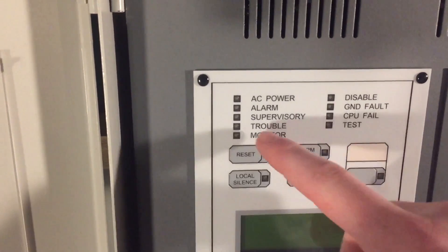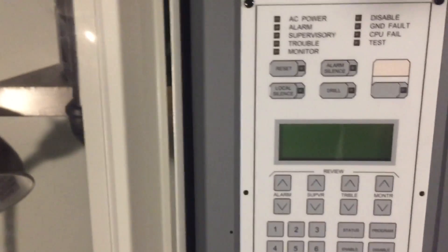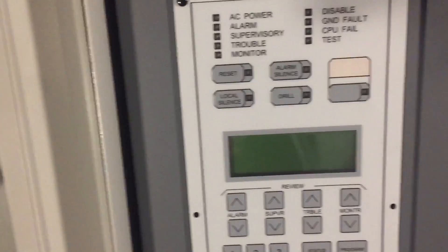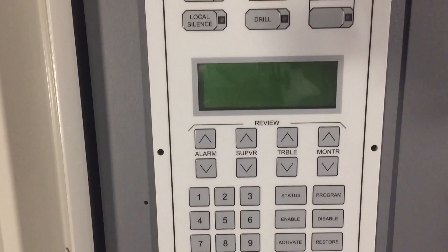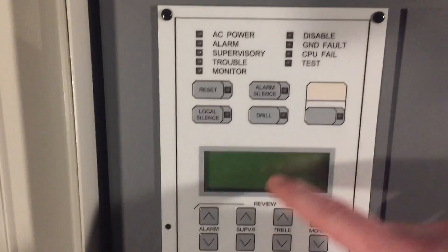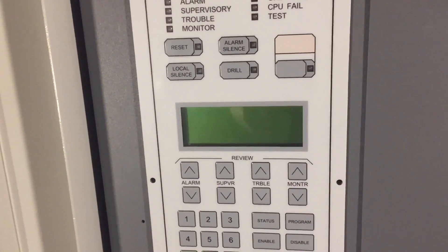Alarm silence obviously shuts off NACs that are programmed to it. Drill is for a fire drill or re-alarm, and reset resets the system. A cool feature about this panel is that unlike your typical panel — like a Fire-Lite type — where alarms and troubles are all in the same event log and you have to scroll through everything, with the EST2 you can scroll through individual event types. So if I had two fire alarms, one supervisory, and a few troubles, I can just go through the troubles, or just the supervisories, or just the alarms. I find that really interesting and pretty convenient.